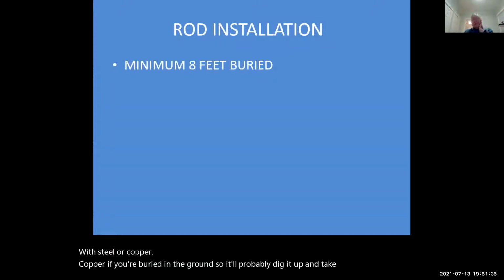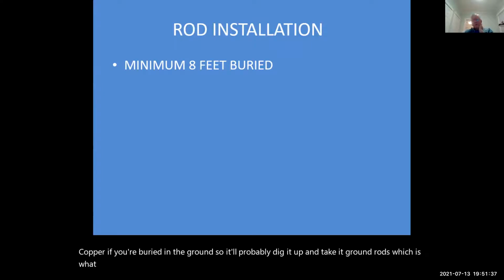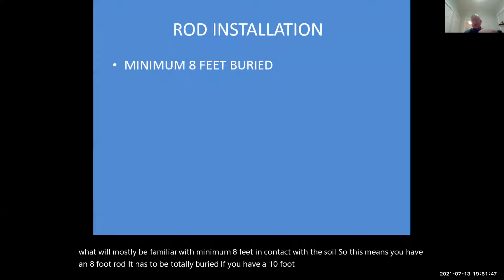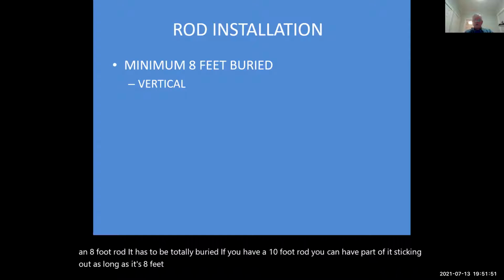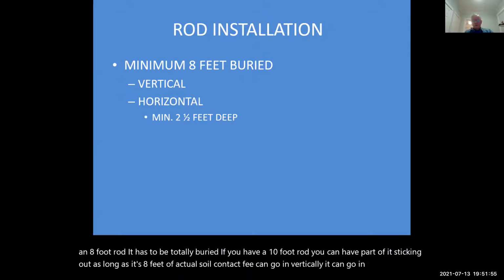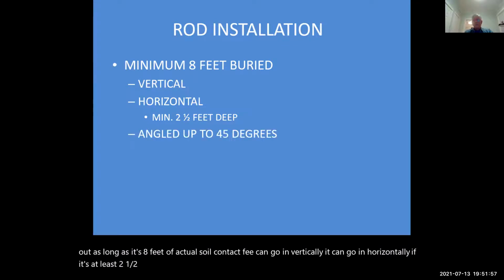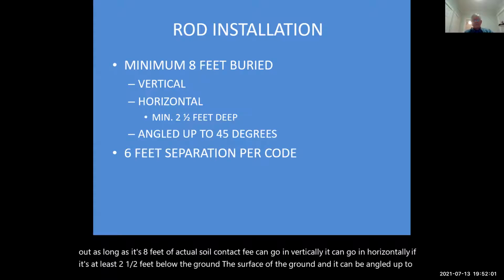Ground rods, which is what we'll mostly be familiar with, minimum of 8 feet in contact with the soil. So this means you have an 8-foot rod, it has to be totally buried. If you have a 10-foot rod, you can have part of it sticking out as long as it's 8 feet of actual soil contact. It can go in vertically. It can go in horizontally if it's at least 2.5 feet below the surface of the ground, and it can be angled up to 45 degrees.